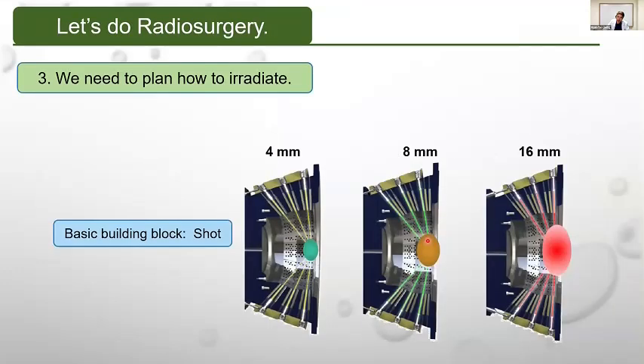Now we know where the tumor is and we can focus the beam. Then it's time to plan how to adjust the beam to the tumor. The building block of this planning is the so-called shot. When you see a certain level of radiation around the center, you can see an elliptical surface like this, and we call this a shot. There are 3 different ones, 4, 8, and 16 millimeters. We use small collimators for small tumors and large collimators for large ones.